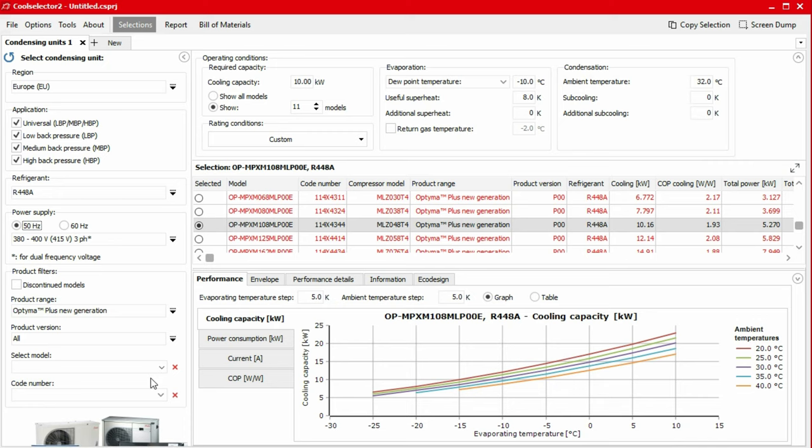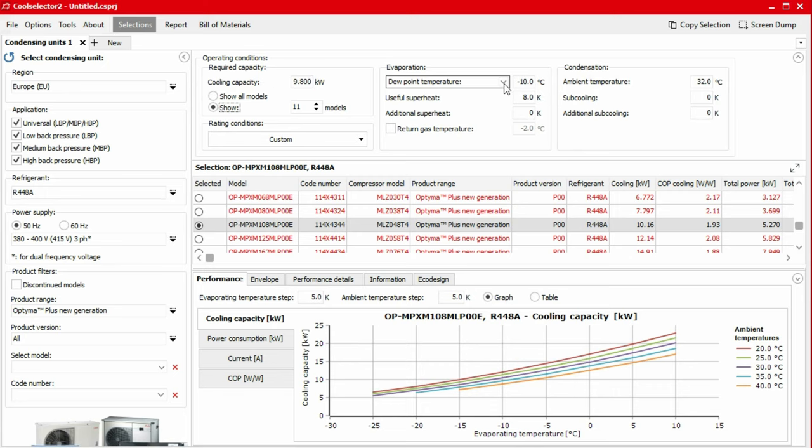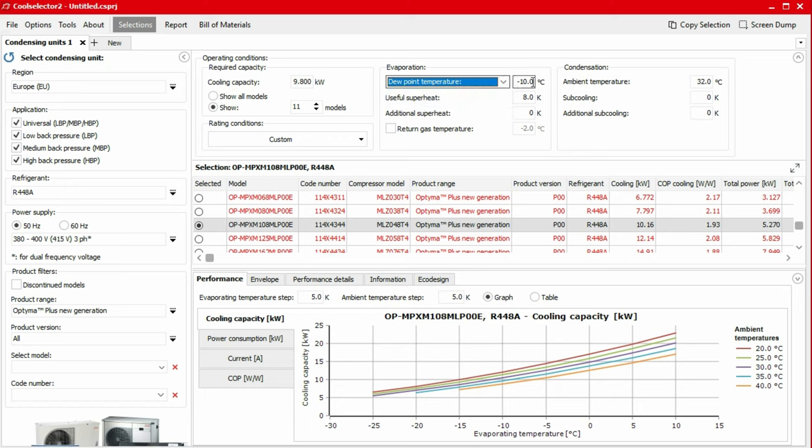Next, we need to specify the operating conditions. We start with a cooling capacity. In this example, we require a cooling capacity of 9.8 kilowatts. For the evaporator, we specify a dew point temperature of negative 10 degrees Celsius. We then need to specify the superheat.